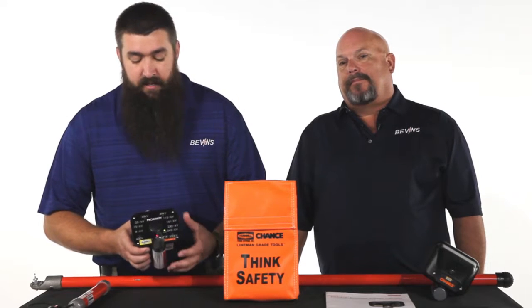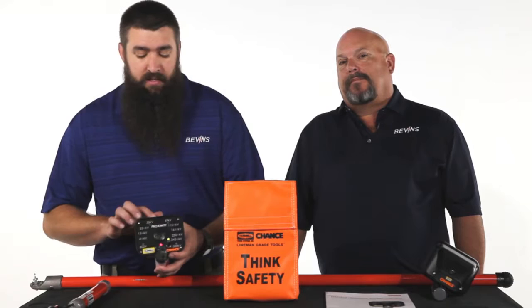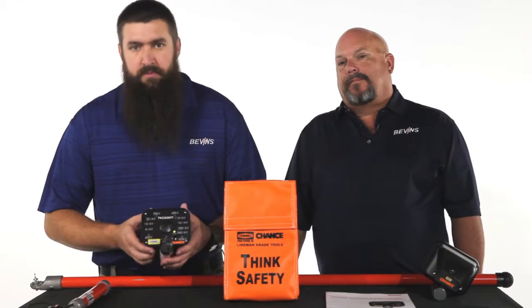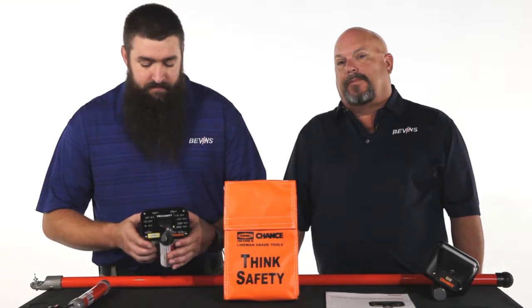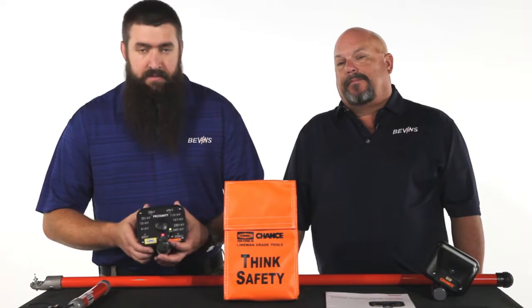We also cannot disable 500 kV on the high side. So if you were to allow the LED to climb all the way to the top, you can't disable 500 kV. Sort of a built-in safety feature there. All right. And to remove the unit from this advanced mode, simply power it down and back up. It will always default to standard run mode. And the same applies to the auto off. If it goes to sleep, per se, then it will always default into the regular mode.